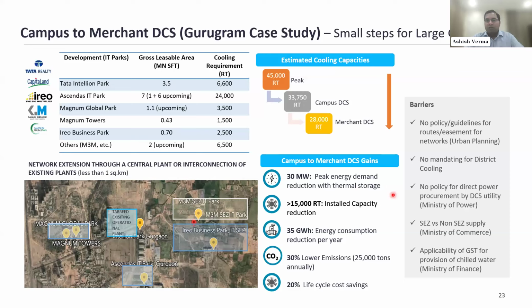But we do have certain barriers, where district cooling is still in a nascent stage. There are no policy guidelines for the network or the easement for the chilled water network. This is very, very important when district cooling has to be incorporated in master plans. There is no mandate for even exploring or doing the feasibility study for district cooling for large master plans. There is no policy for direct power procurement by the DCS utility. Then we have complications with respect to SEZ versus non-SEZ, and then again, the applicability of GST when the chilled water is being supplied to multiple customers.